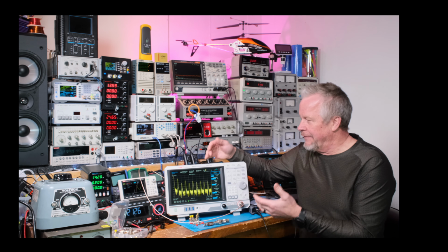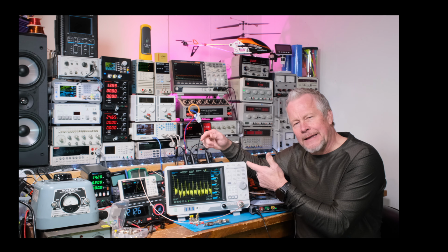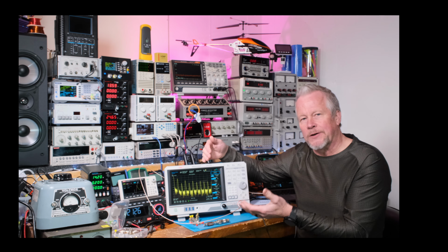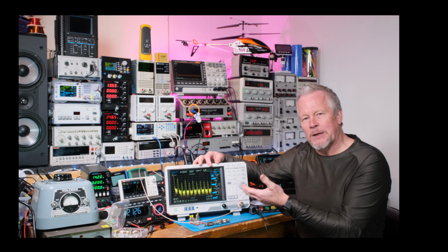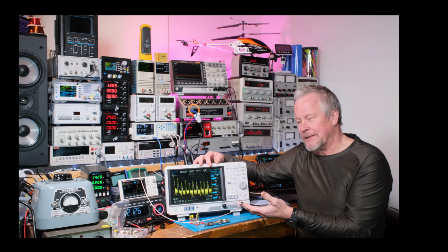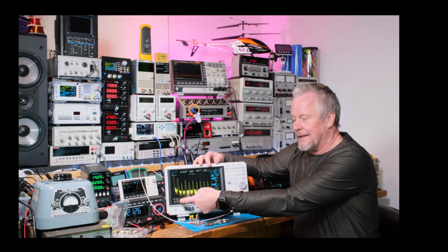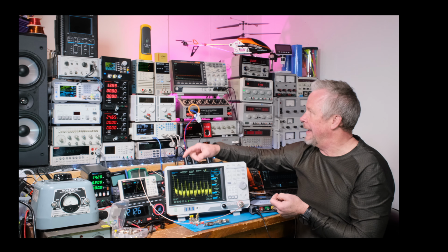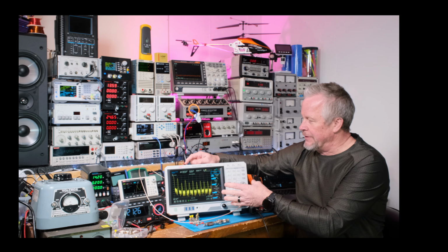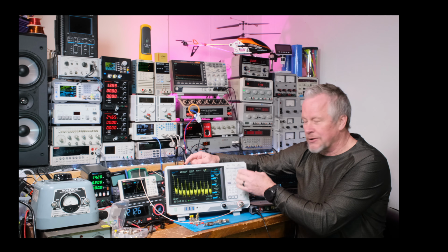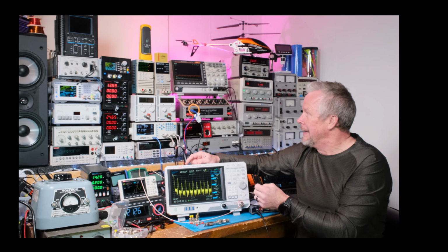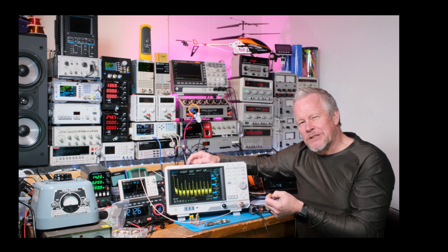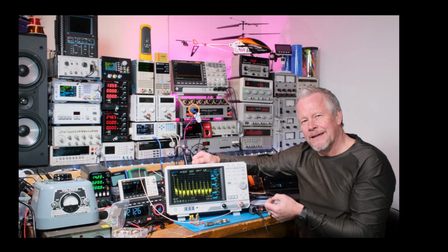Alright, so I just did a video that I posted introducing the Spectrum Analyzer, showing how to take your first measurement. Now, a spectrum analyzer is different from an oscilloscope, right? It has a spectrum of frequencies versus decibels. And I showed you how you set up the scope, how it works a little differently than a scope.